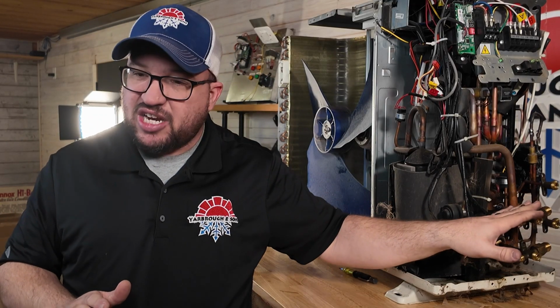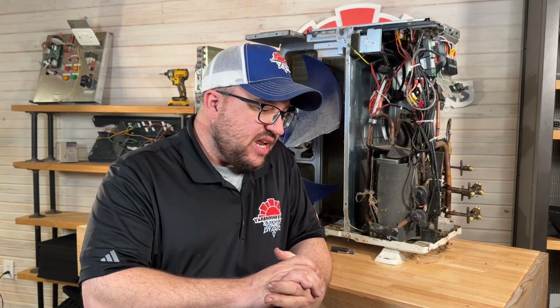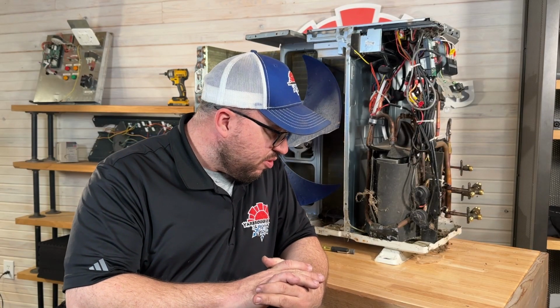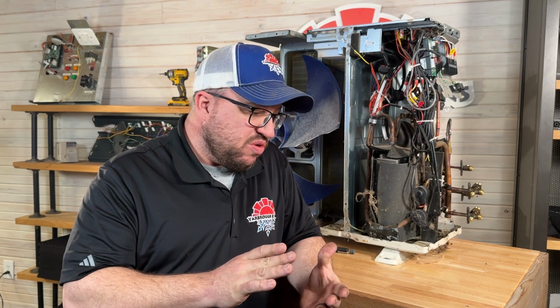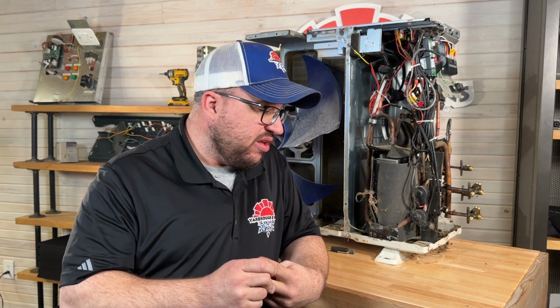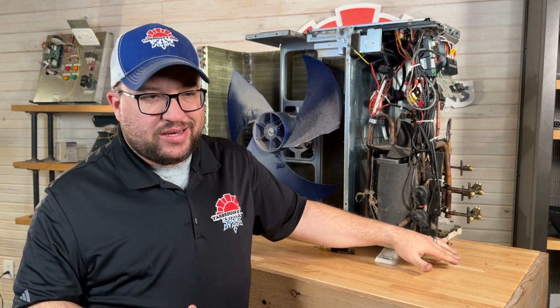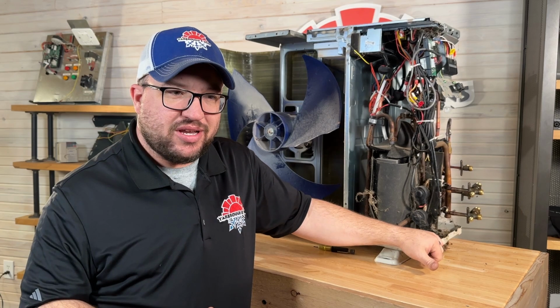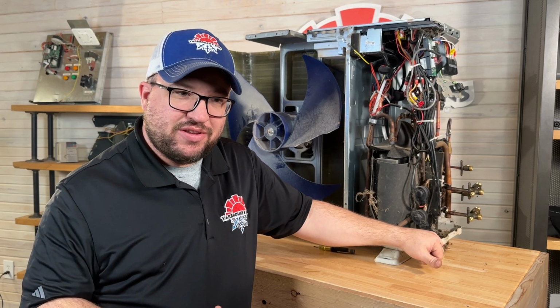Like I said, this is a multi-head, and it's actually 1.5 tons for air conditioning, so 18,000 BTUs. With that, what happened with this customer was it was tied in with two 1-ton heads, so that's 2 tons of air you'd be putting into that house. Well, if you tie it with 18,000 BTUs, 1.5 tons, you're not going to get 2 tons of air out of it.